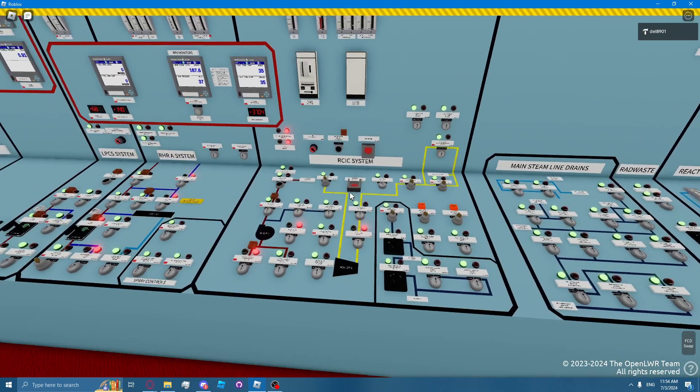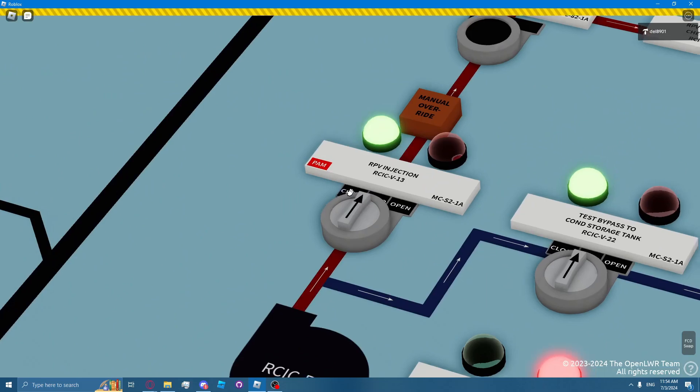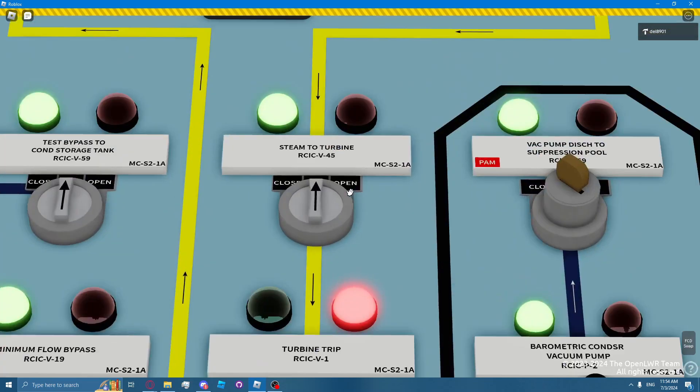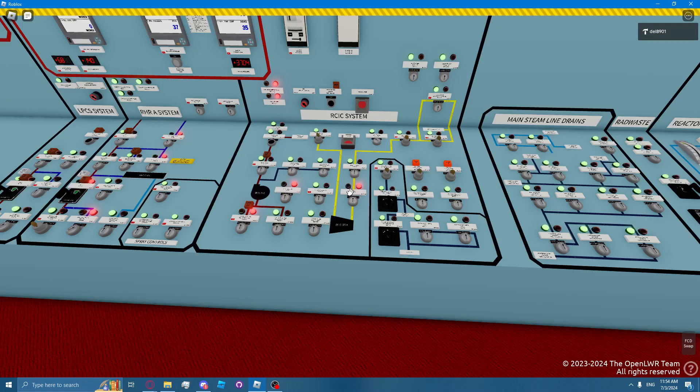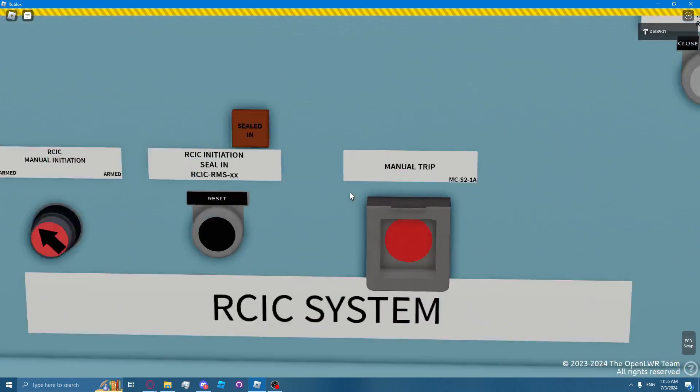Additionally, the main turbine trips when RCIC valve 13 and RCIC valve 45 are open. The RCIC turbine will trip on overspeed, which is greater than 5,625 RPM, low suction pressure, high turbine exhaust pressure, any isolation signal, and manually tripping the RCIC turbine.